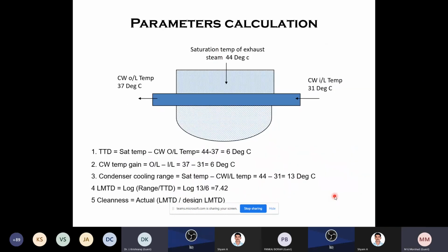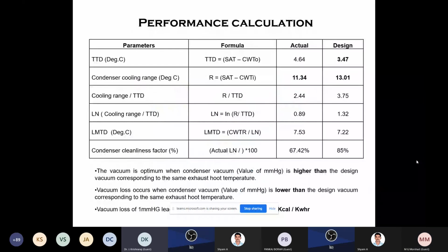Now this is the condenser I have given: the saturated temperature, the inlet water and outlet water. So TTD, what I am telling you, LMTD, everything you can calculate, and you can see these are all the parameters whose calculation I have done here. Finally, condenser cleanliness will be the factor. Design is 85%, ours is 66, 67%. That means the condenser is not clean. It may be external, tube fouling or something.